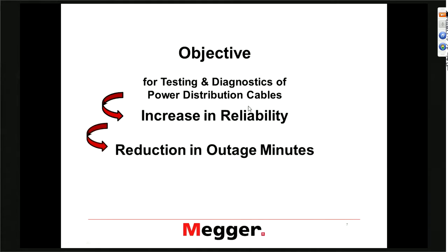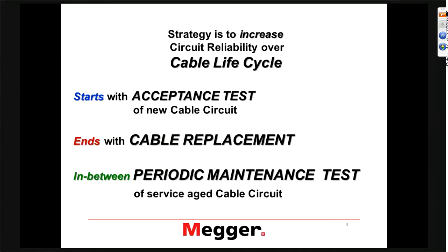What is the objective of testing and diagnostics of power distribution cable? We want to increase the reliability, and as a consequence, also have a reduction in outage minutes. This is pretty much a driving factor in today's business environment in the utility industry. The strategy to increase circuit reliability over the cable life starts with the acceptance test of a new circuit, ends with the cable replacement, and in between we have the periodic maintenance test of service-age cable circuits.